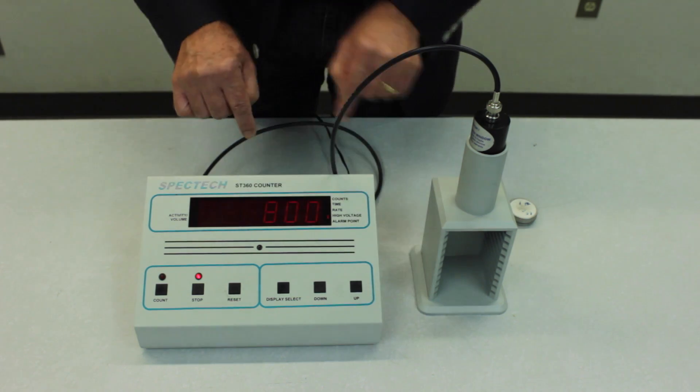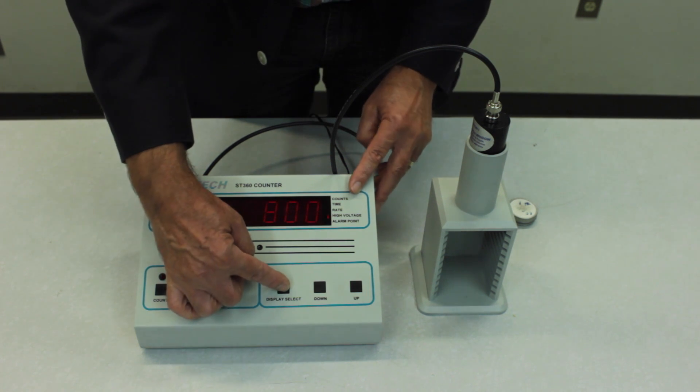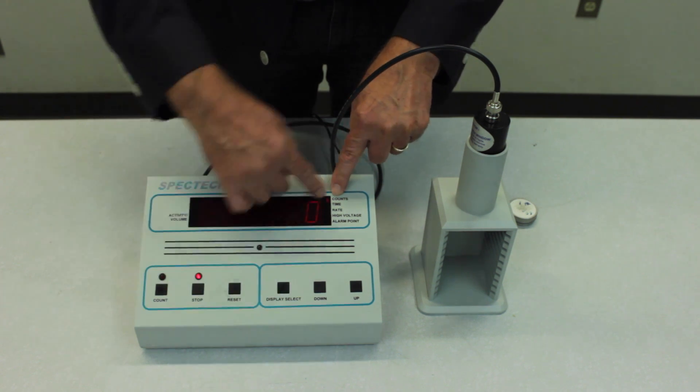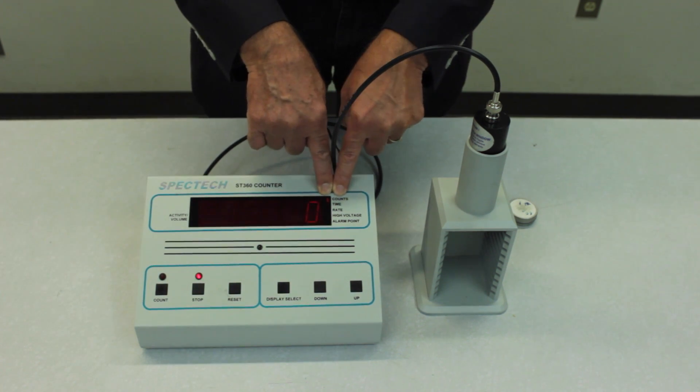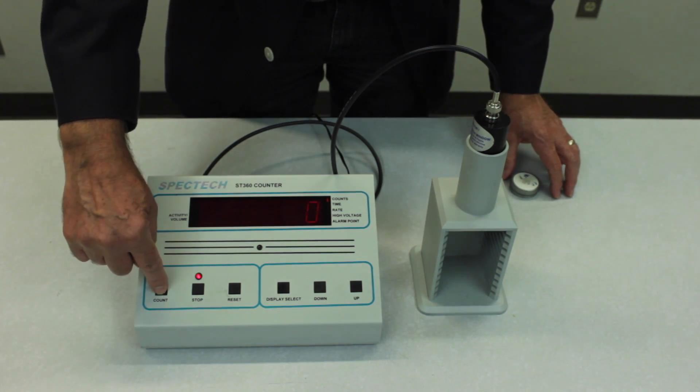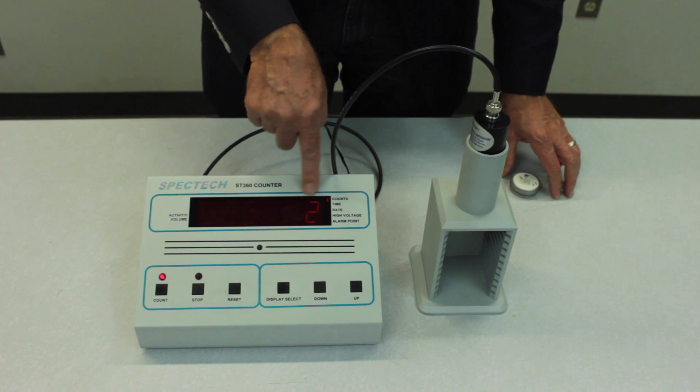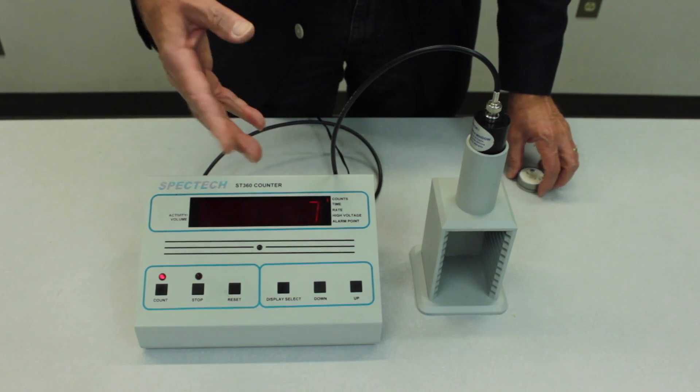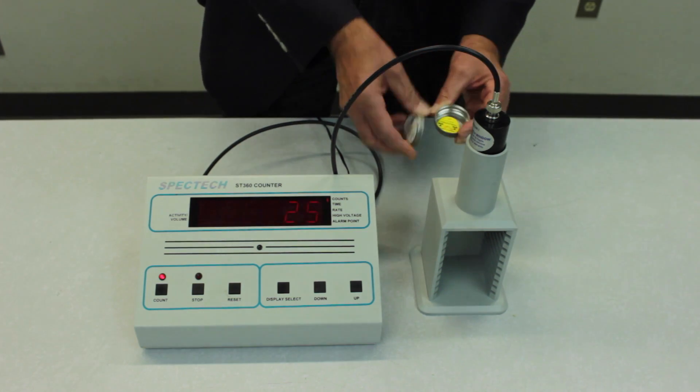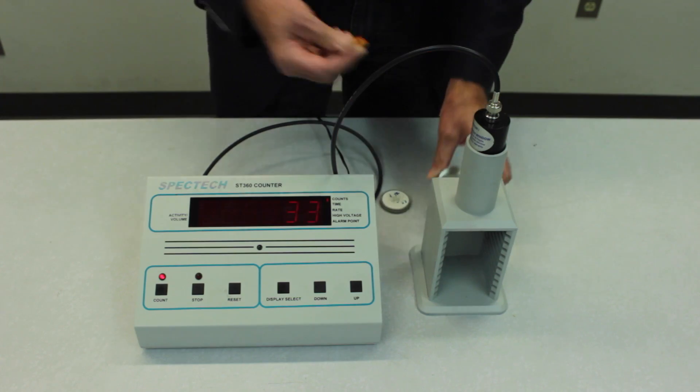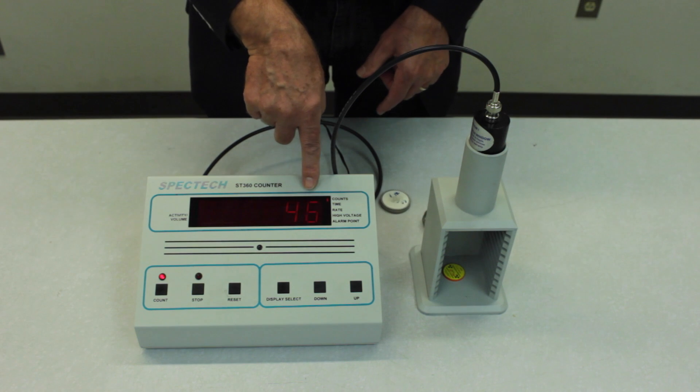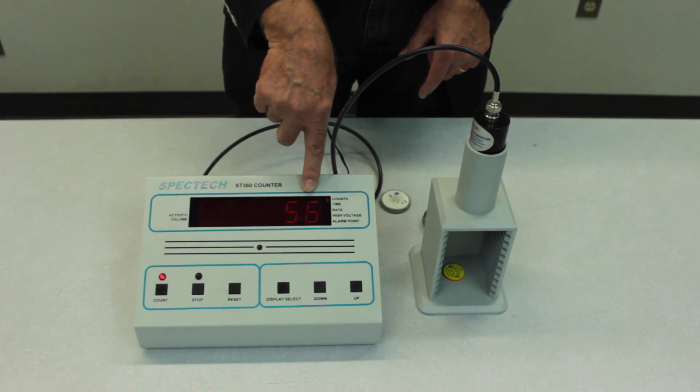And once you've set the voltage then you press the display select button again. Actually press it two more times to get it back to the count function. And we start a count. So you press the count button to begin. And what we're doing now essentially is counting basically background radiation. The source is far from the detector. But once we put the source in the chamber then the counts begin to accumulate at a much faster rate.